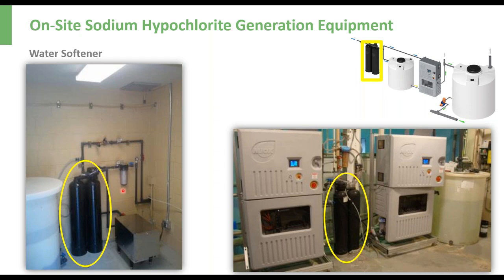And what's cool about these, the ones that we particularly use, but a lot of manufacturers do, is it's a non-electric process. On top of the softeners, there's a little gear head. When a system is started up initially, we will take hardness level samples of the water being supplied to our system. There are different gear ratios depending on your hardness level. It's an old school gear: water passes by that gear and turns it. When it gets to a certain turn, it says, okay, this resin is spent, we need to replenish it. So it will switch to the tank that was in standby.